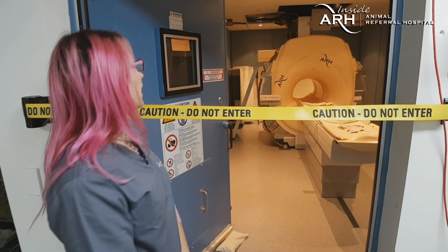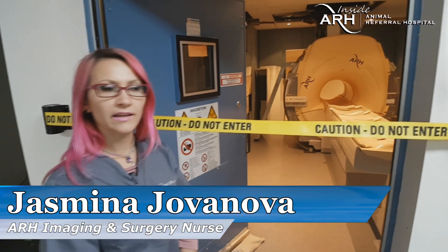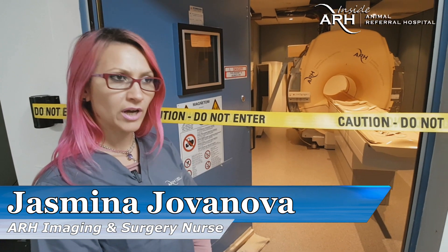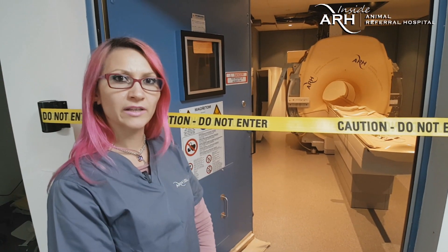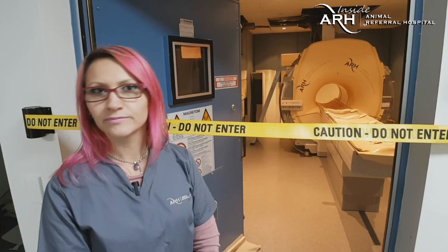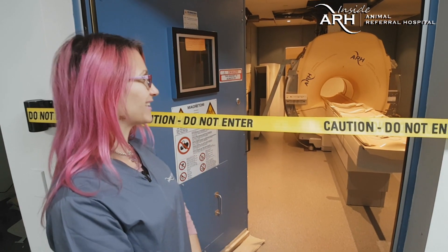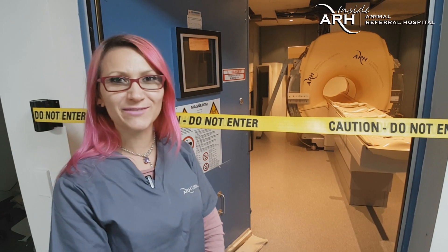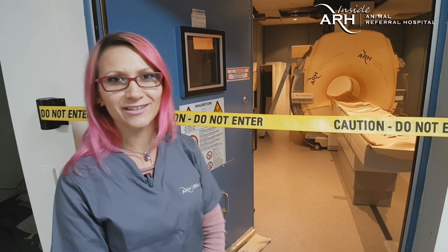ARH Imaging Coordinator and Surgical Nurse Jasmina explains: 'We are going to be in the process of quenching the MRI today, so we can install a newer, better model MRI. We're going with a Siemens Avanto with 1.5 Tesla. We need to quench this one, remove it, and then install the new one.' Is it scary? 'It's more scary than exciting. But it's a new experience for me, and for the hospital.